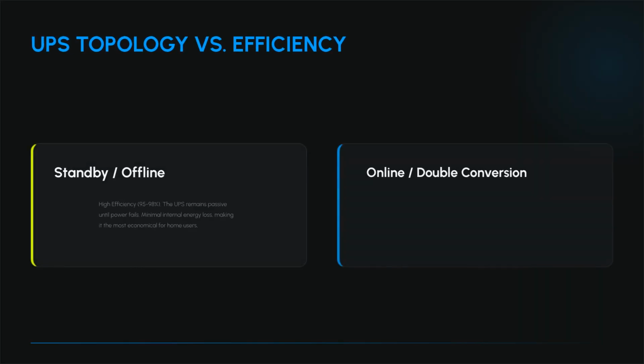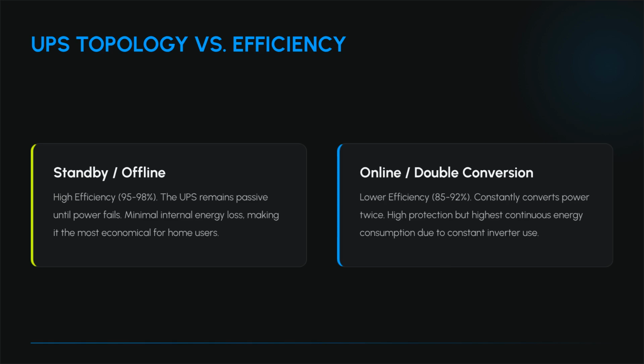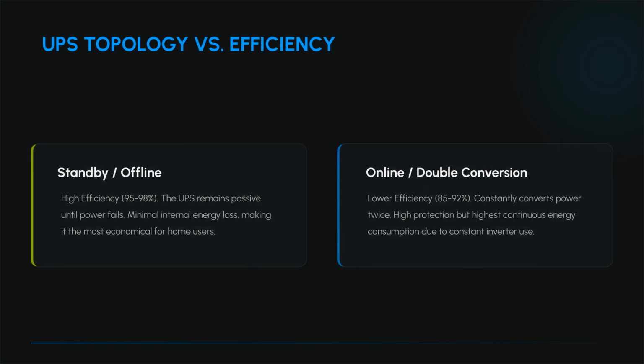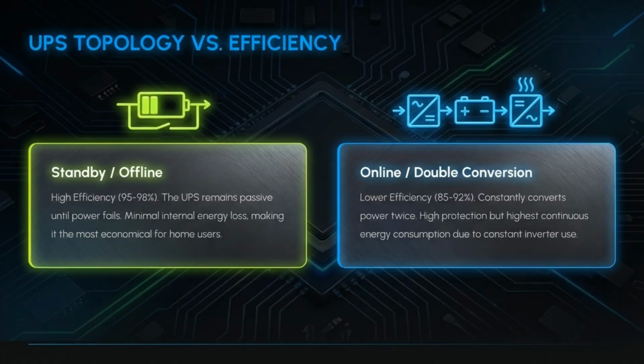UPS topology significantly impacts efficiency. Standby or offline units are highly efficient at 95 to 98% because they remain passive. Online or double conversion units are less efficient at 85 to 92% due to constant power conversion. The design of the UPS dictates the level of continuous energy consumption and protection provided.